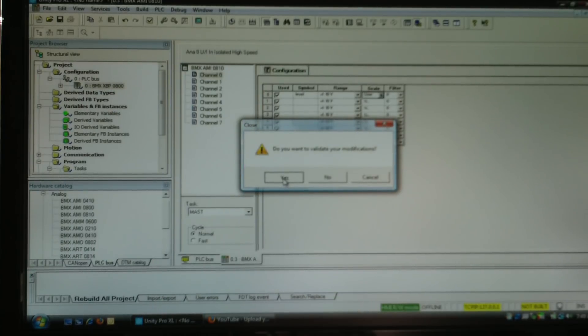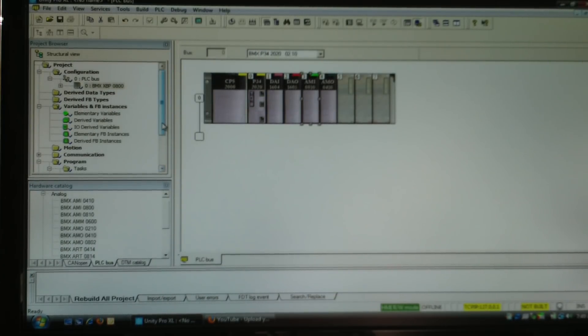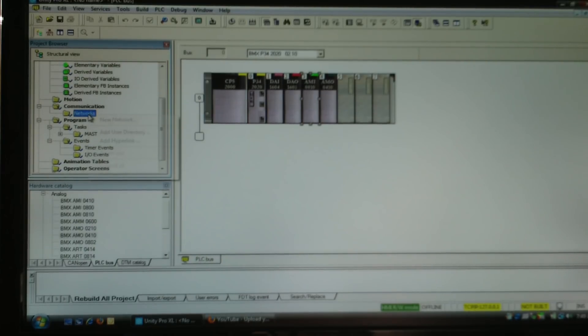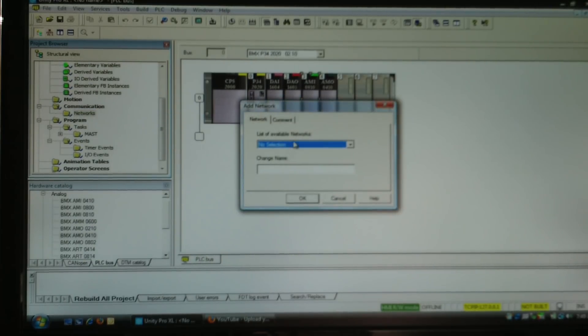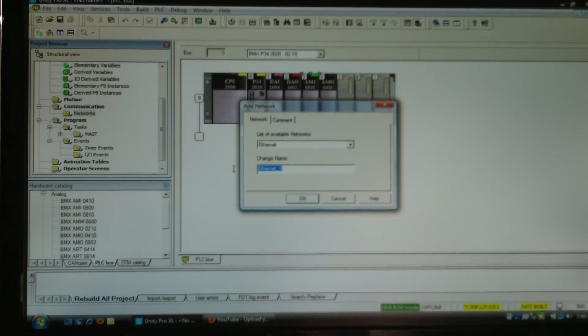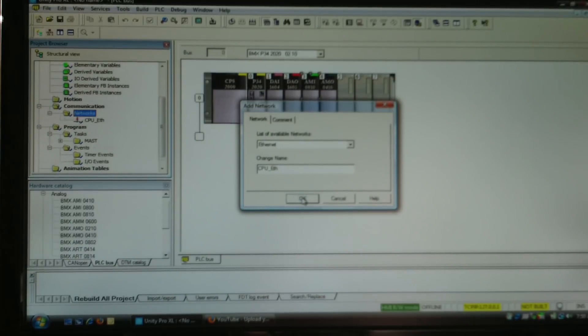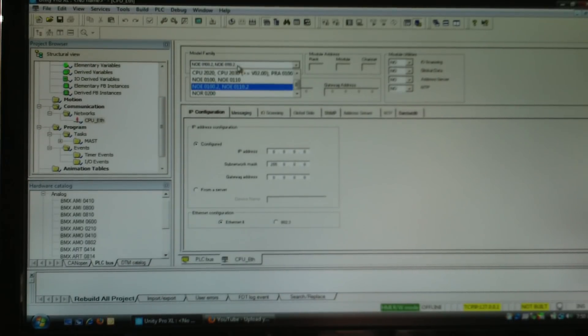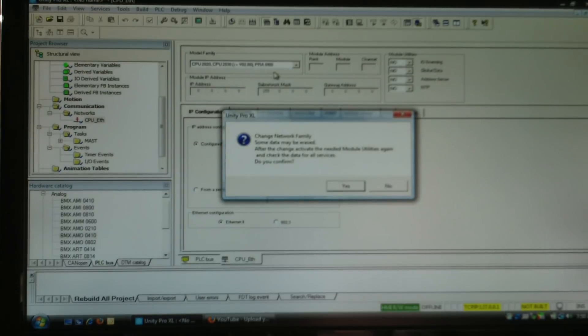The other thing I need to configure on my hardware is my network. I'll go to Communications > Networks, right-click, select New Network, choose Ethernet. It gives me the name 'ethernet_1' — I can change that; I'll call it 'CPU ethernet'. That gives me my network, and I can double-click it. By default it has a model family of NOE; I want to select CPU.